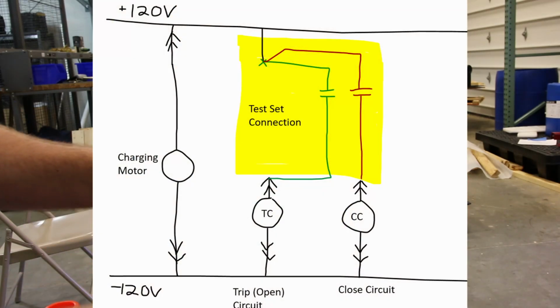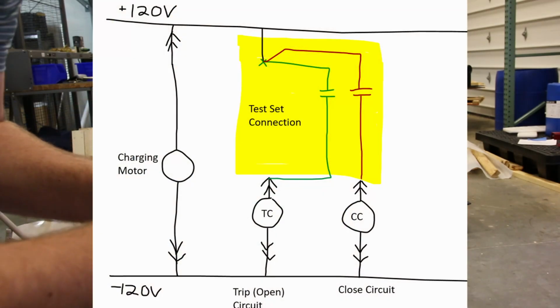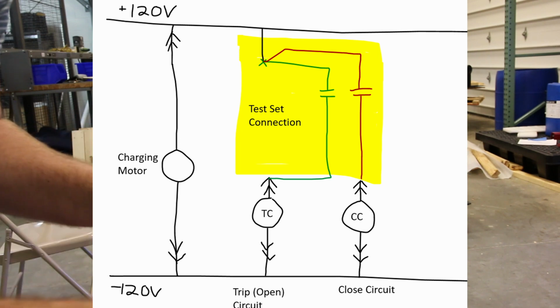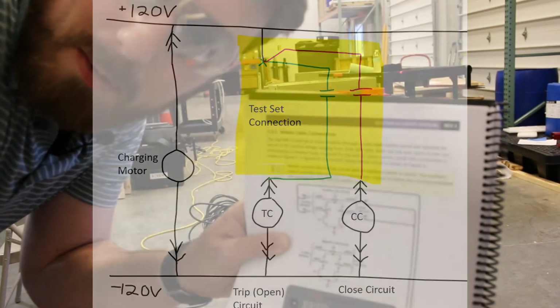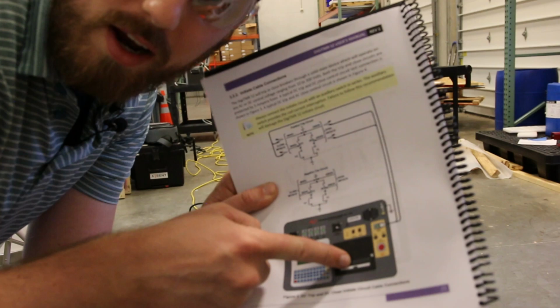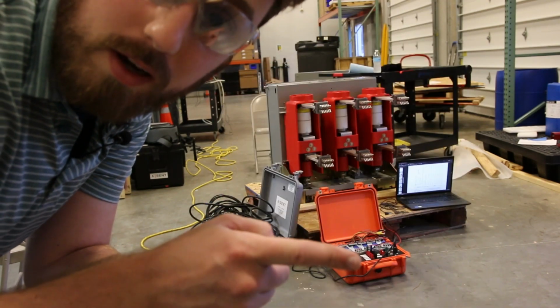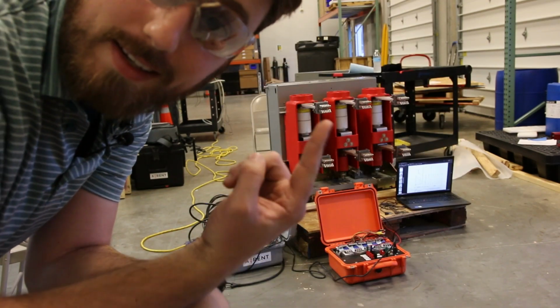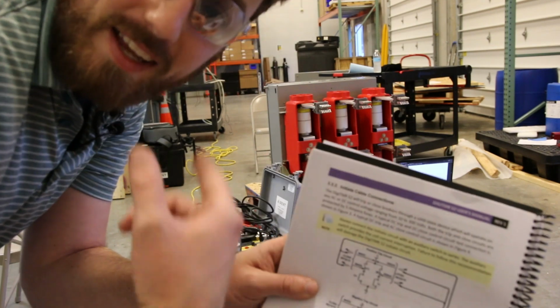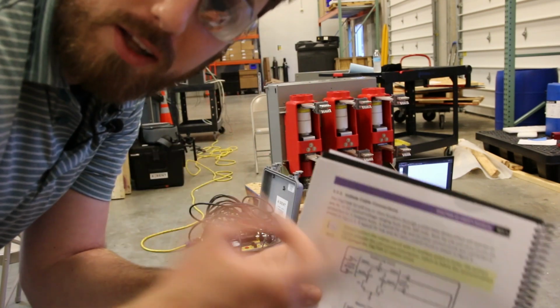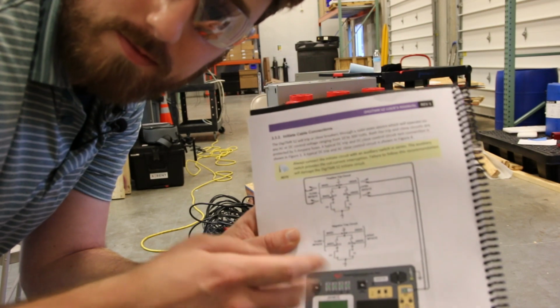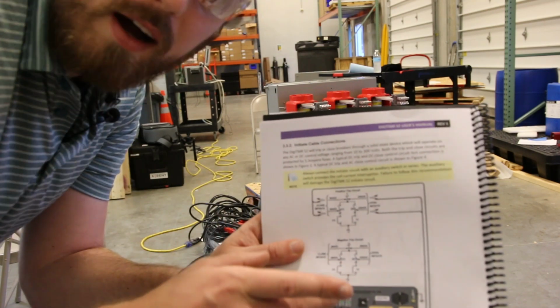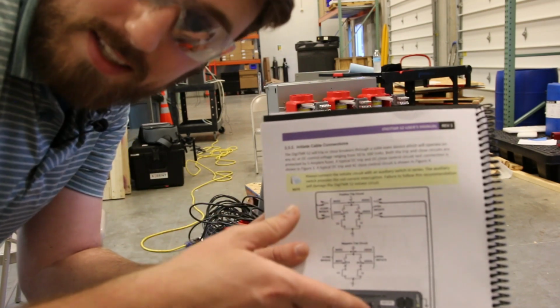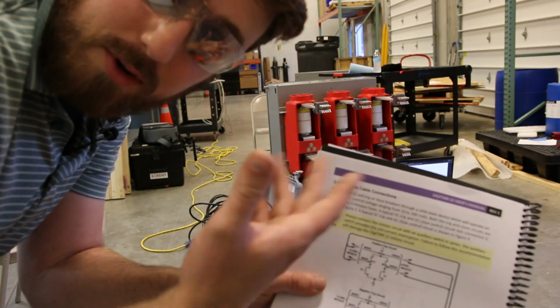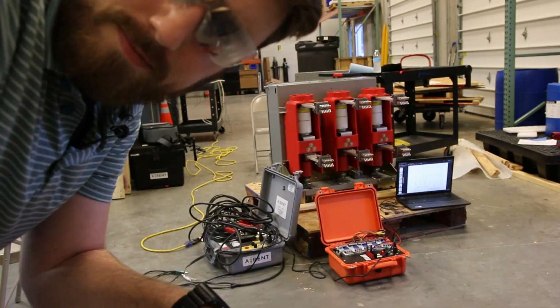I might put a graphic up on the screen here-ish with how I'm connected to this one where it combines the two. What we really need to do is come up with a drawing of what this is trying to do and what the breaker wants connected to it. We can let the charging motor run, we close the breaker and have the test set tell it to close and time it. And then we tell the test set to trip the breaker and record the time that it takes to trip.